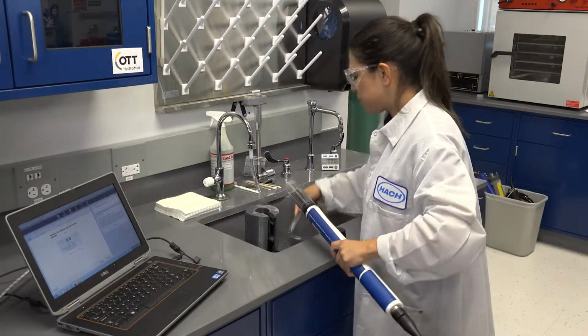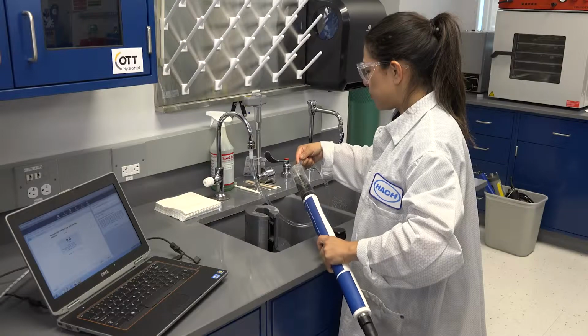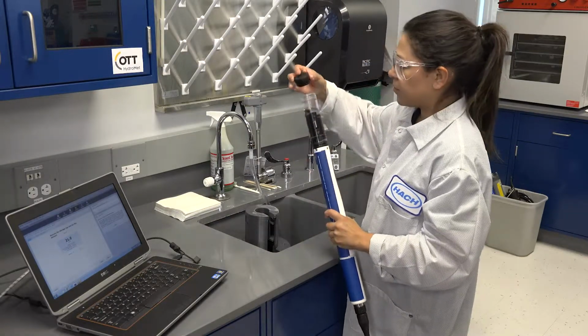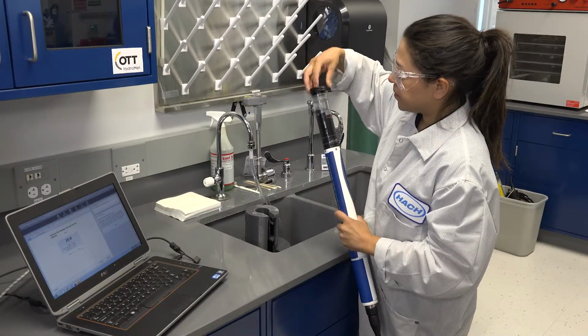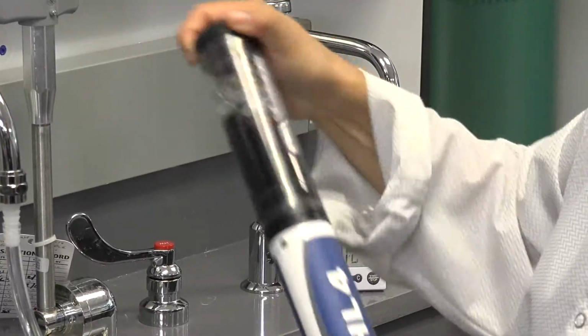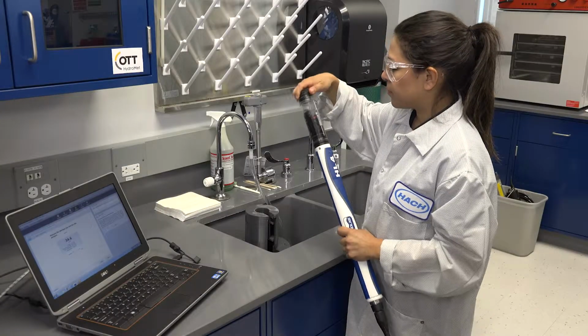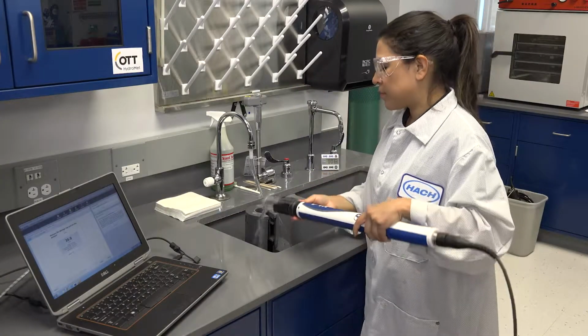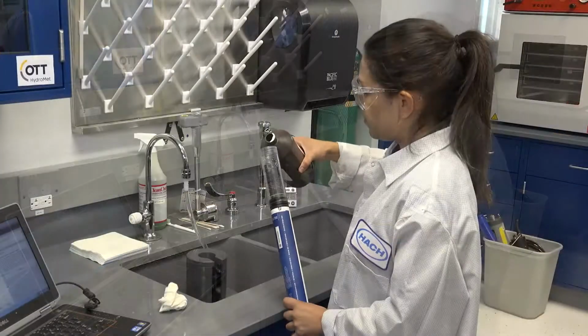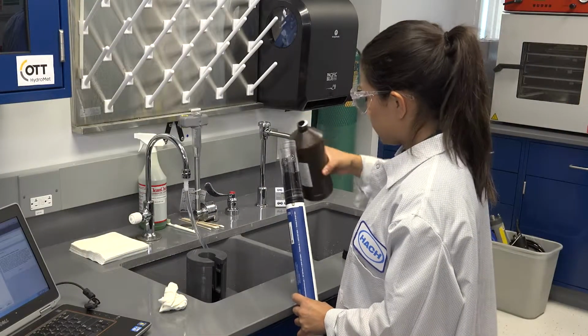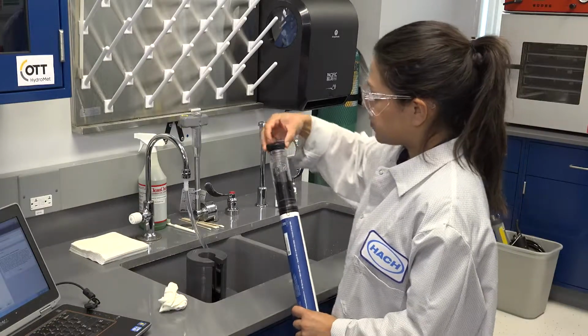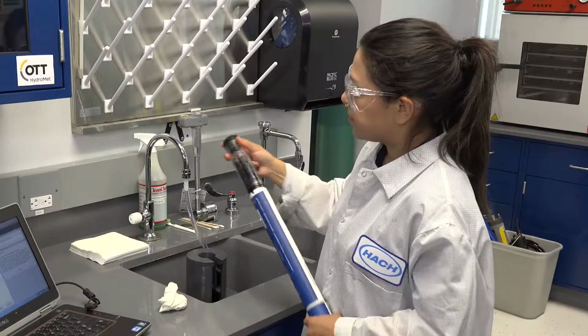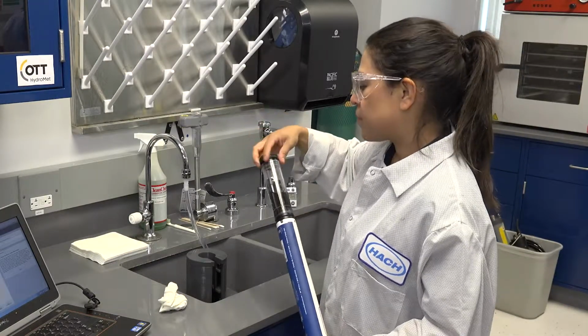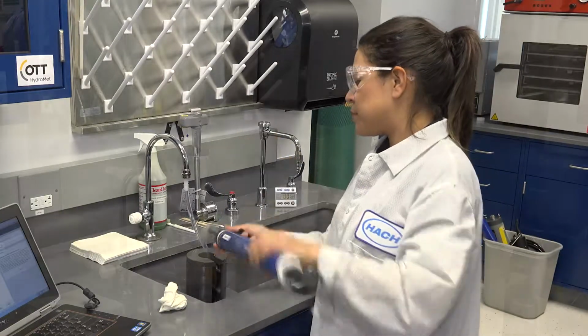Rinse 3 times with deionized water by pouring a small amount of deionized water into the calibration cup, replacing the cap, and shaking vigorously for approximately 6 seconds. Now rinse 3 times with the desired standard by pouring a small amount of the conductivity standard into the calibration cup, replacing the cap, and shaking vigorously for approximately 6 seconds.